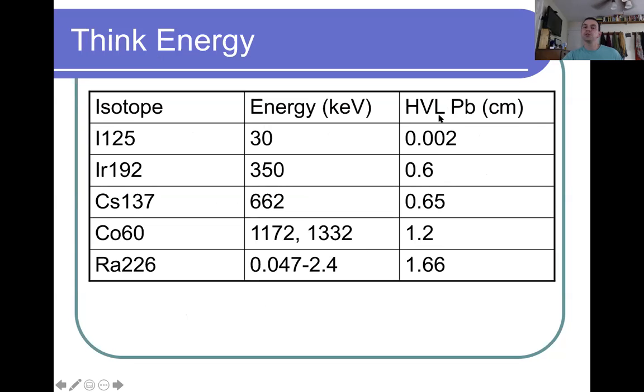Unfortunately, we usually do shielding before this lesson, but I'll do this half value layer. Think of that as kind of like a half-life. It's not the amount of time, it's the amount of material you need in place to reduce the radiation present to half. It works in much the same way as half-life and radioactive decay. You're essentially trying to reduce the intensity of the radiation a number of times in order to bring it down to a safe level. Something like I-125, a very, very small amount of lead will cut that radiation by a significant amount, versus something like radium or cobalt, where you need inches of lead to deal with high activity sources.